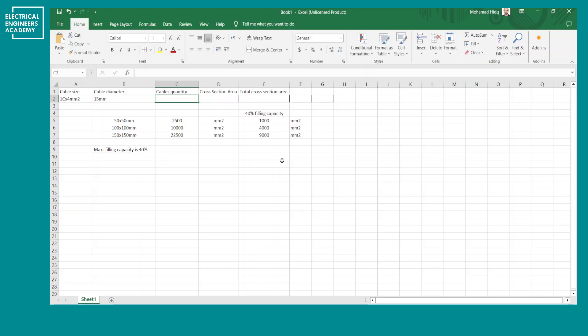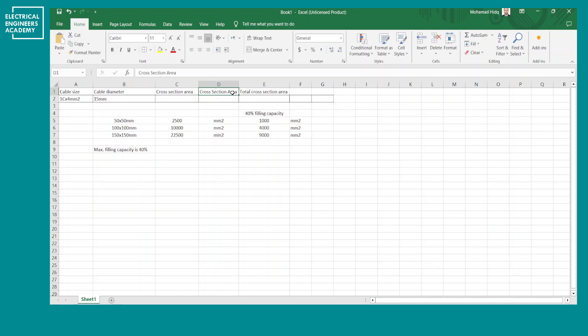You can approach this two ways: if you want to check how many wires you can put in a certain trunking, calculate the cross-sectional area of one wire and divide the permissible filling capacity by that area. Alternatively, if you have a certain number of wires, multiply by the single-wire area to find the total area occupied and then select the appropriate trunking size.